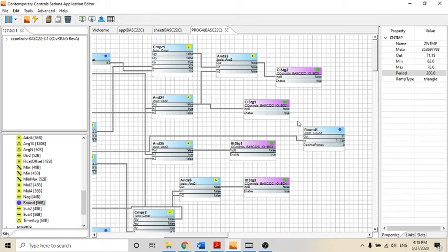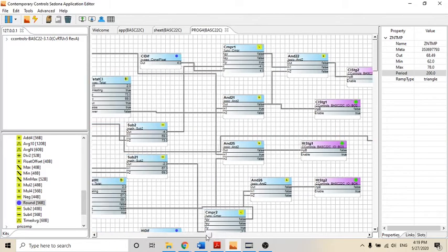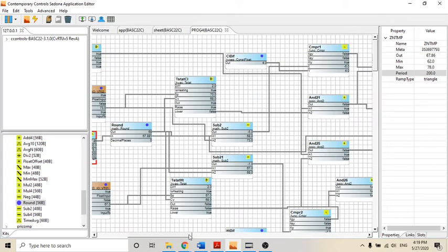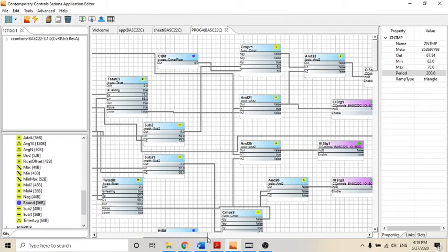We are no longer cooling, and we are not heating yet. So we go down through the dead band, and again the dead band is going to go all the way to 67 degrees, which is when the effective zone heat set point is.